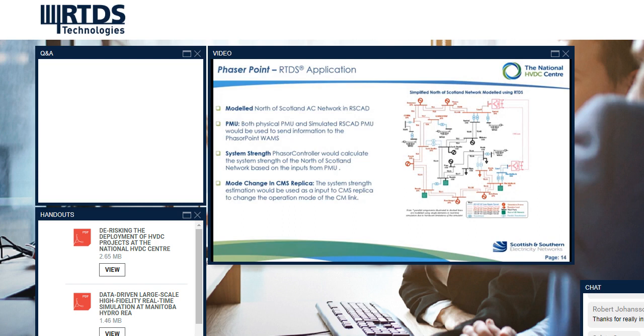The physical PMU would get the measurement from the model using a combination of GTAO card and power amplifier. These measurements would be further transmitted to GE's Phasor Point wide area monitoring system using IEEE C37.118 protocol. While the simulated RSCAD PMU would directly relay the information to GE's Phasor Point wide area monitoring system using the same IEEE C37.118 protocol.